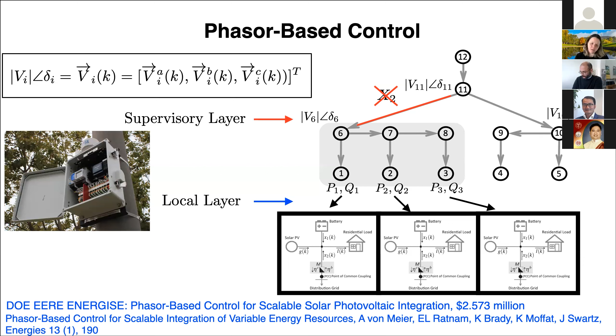So there's a lot of different things we could do with the supervisory layer. If it assigned those two phasors to be equal, we could adaptive island. If it set them to restrict power flow, we could do the same as before, like reduce the power across the transformer by 2 megawatts.